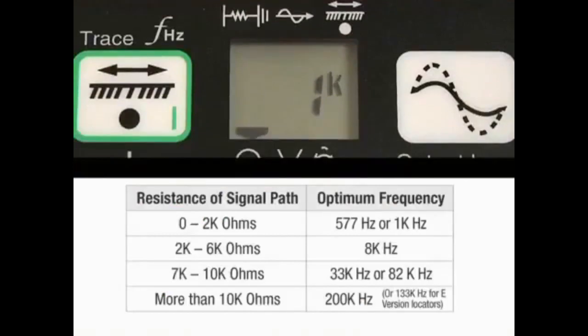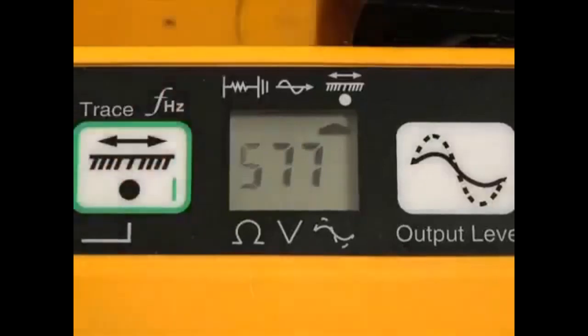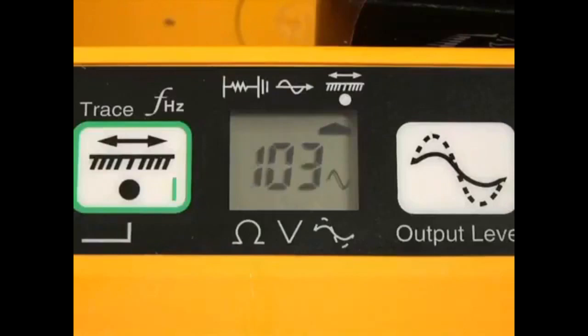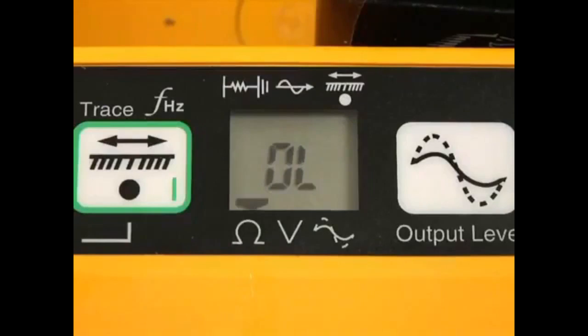In the previous example, the resistance of the signal path was 1 k. Based on the reference chart, the optimum frequency for this locate would be 577 Hz. You should always select the lowest frequency applicable to the resistance of the signal path, because the lower the frequency, the less chance of bleed over signal to adjacent facilities. If the resistance of the signal path is greater than 10 k, or if the ohmmeter displays OL, this could be an indication of an open line or that the return path through the ground is very marginal or nonexistent.